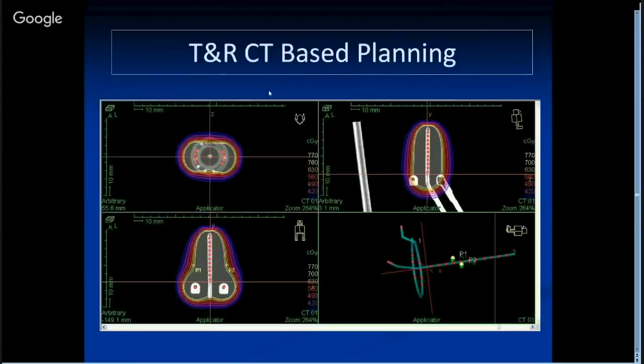Here is an example for tandem ring, this kind of CT-based planning. Here's the ring, you can see clearly, and you need to use a dummy source. You can define the first wire position — here is the first wire position. Then you need to identify the catheter, do reconstruction for each catheter, activate your source dwell positions, and then define a left A and right A point, and then do optimization.